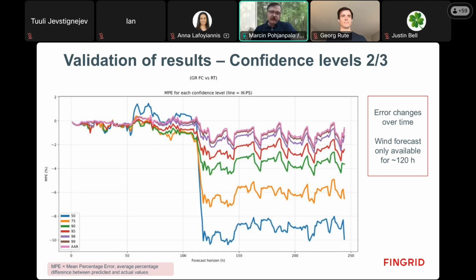Then when we get past 60 hours, that's 2.5 days, we change the weather model, and we get into a higher error level. That's just because different models have different attributes. Roughly at 120 hours, we no longer have the wind forecast, which is why the error goes so high. So it's not that the model failed, it's just that the base assumptions changed.